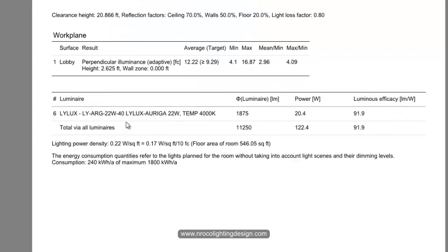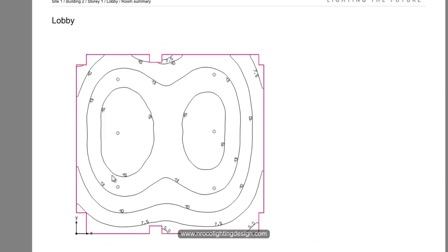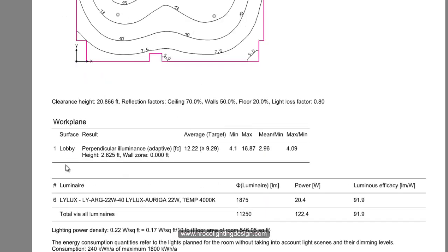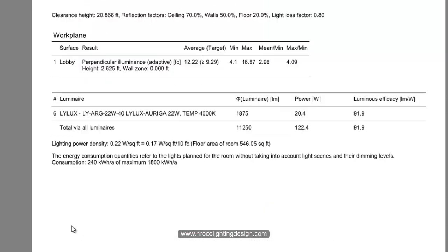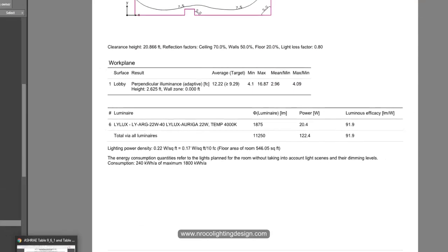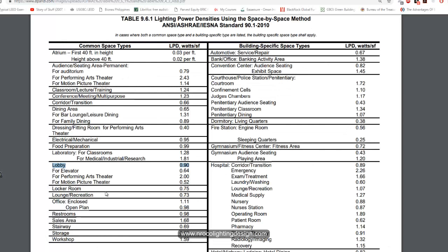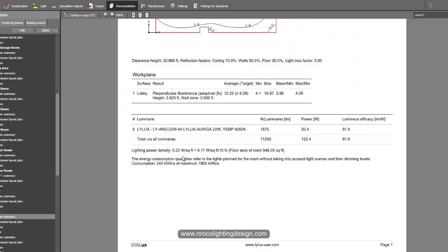So it's 0.22 watts per square foot. This is the lighting power density of this lobby area with six downlights. Based on the requirements, lobby is 0.9, so 0.22 is much less than the requirement. This means this lobby has achieved the LPD requirements as per ASHRAE.